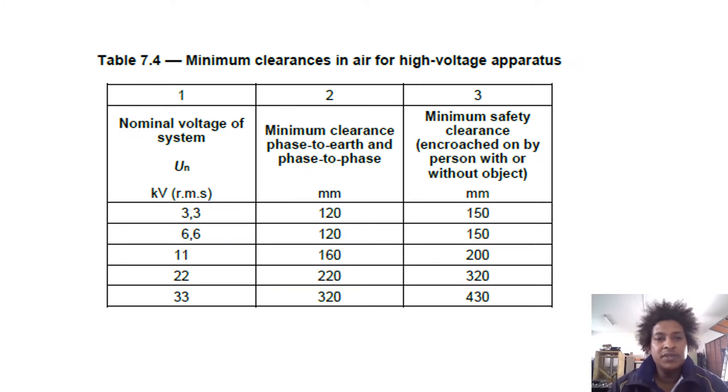Table 7.4 shows minimum clearances. At 3.3 kV, the minimum phase-to-phase and phase-to-earth clearance is 120 mm, and the minimum safety clearance for a person with or without an object is 150 mm. At 6.6 kV, the same applies: 120 mm and 150 mm. At 11 kV, the phase clearance is 160 mm.